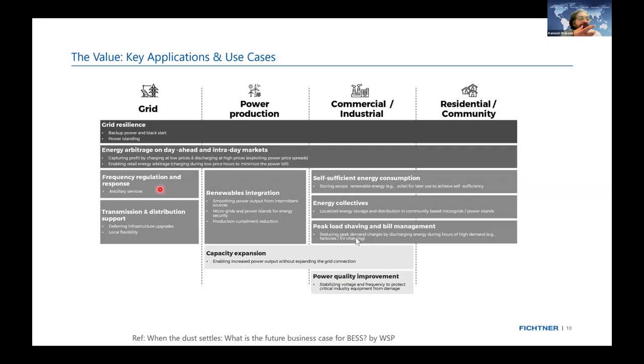So probably you'll have 50.5 as an over-frequency relay. I don't want to operate that, so I need to shut down the unit. At 50.1, I will absorb the power from the grid. So initially I will inject, now I will absorb. This flexibility I will bring with the help of a BESS into the grid.